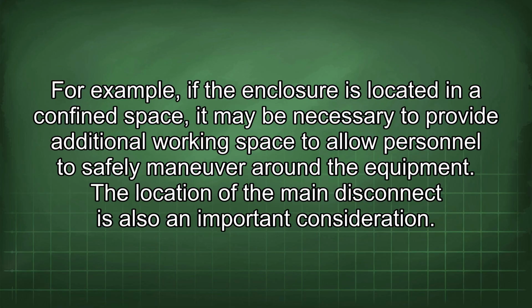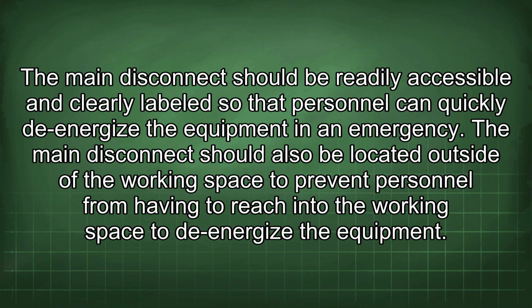The location of the main disconnect is also an important consideration. The main disconnect should be readily accessible and clearly labeled so that personnel can quickly de-energize the equipment in an emergency. The main disconnect should also be located outside of the working space to prevent personnel from having to reach into the working space to de-energize the equipment.